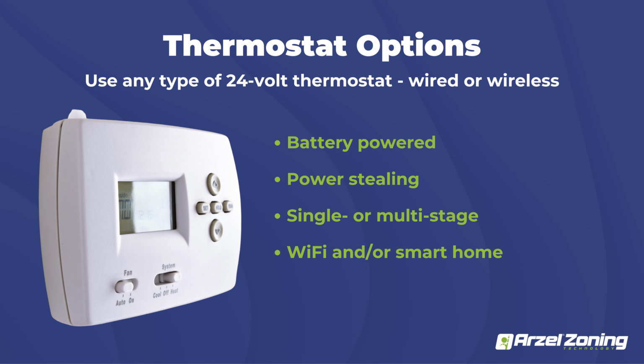If you're going to do Google Nest or EcoBees or anything like that, just make sure you're staying away from wire saving kits, and make sure you're using your designated common wire to the thermostats. Zoning panels in general don't work very well with wire saving kits because of the way they function, stealing their voltage from whatever function you're not using. So if we're running cooling, it's actually stealing power from the heating circuit, and that can create what we call phantom calls, where it energizes that W call with a cooling call because it's stealing that voltage, and the panel's not going to serve that call because it's going to treat it as an illegal call, or a call that the panel will not recognize. So if you're going to use those power stealing stats, just make sure you run a common wire, and you'll be good to go.